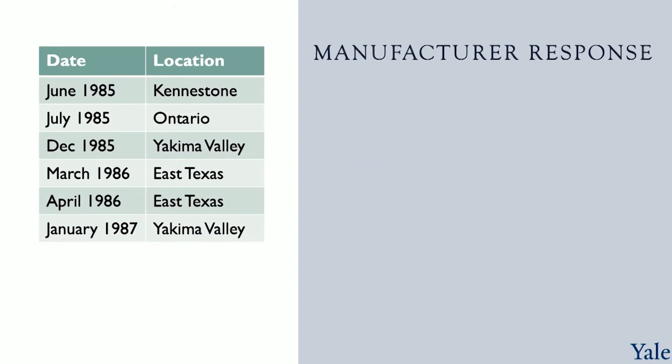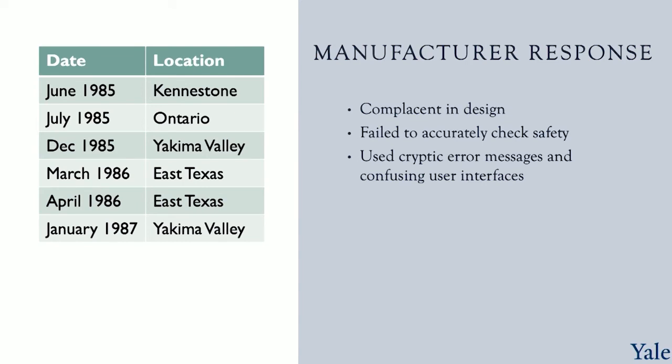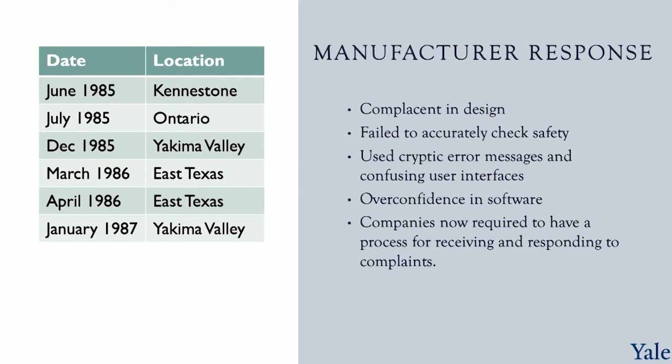We can learn a lot from the failures of the manufacturer to respond to complaints. They were complacent in design and failed to accurately check safety, assuming that since prior versions were safe, the new version was safe as well. They used cryptic error messages and confusing user interfaces. They were overconfident in their software, failing to conduct adequate investigations following hospital incidents. These failures led to severe injury and death for several individuals. Because of these incidents, companies are now required to have a process for receiving and responding to complaints.